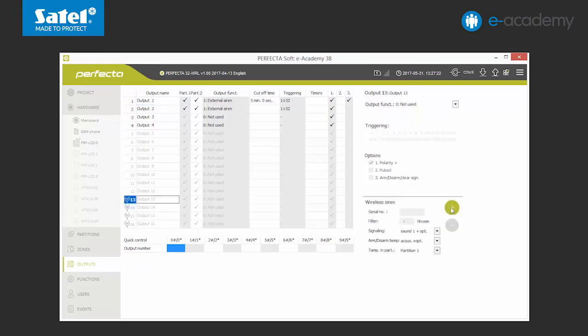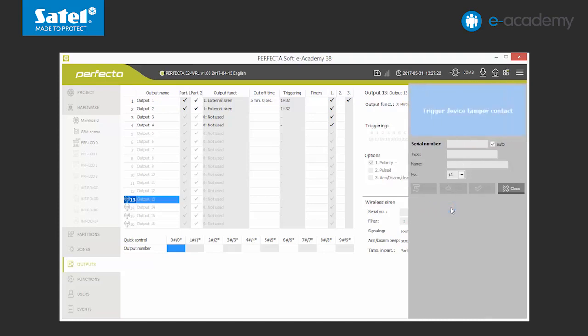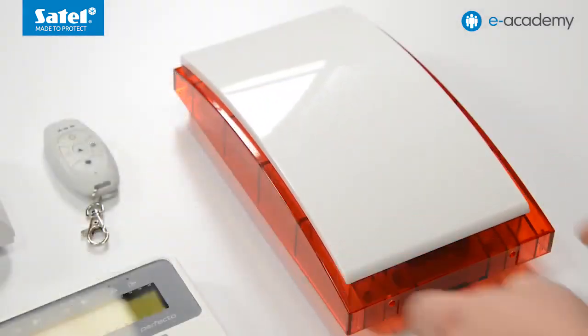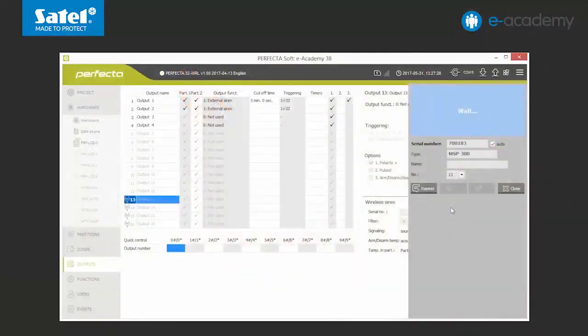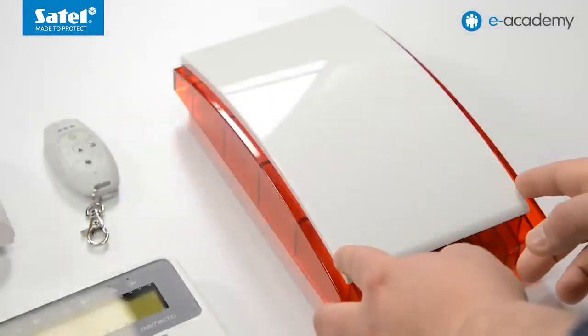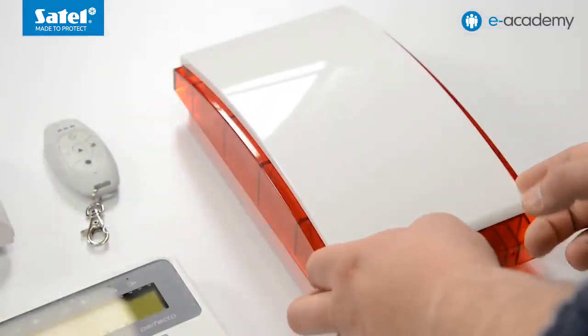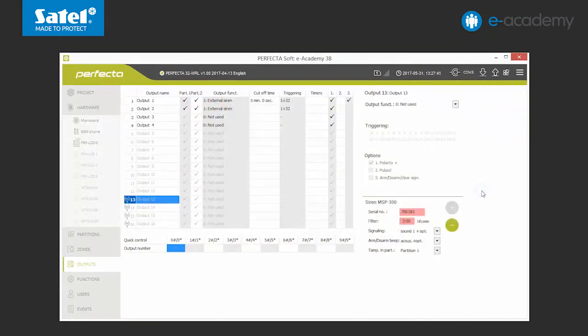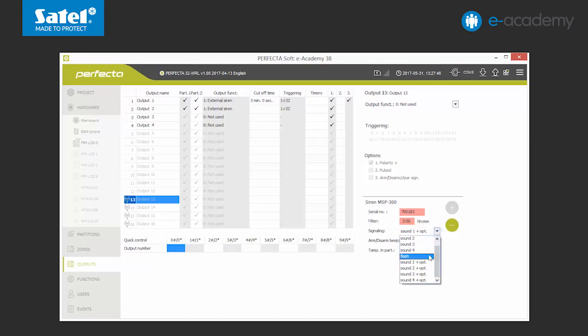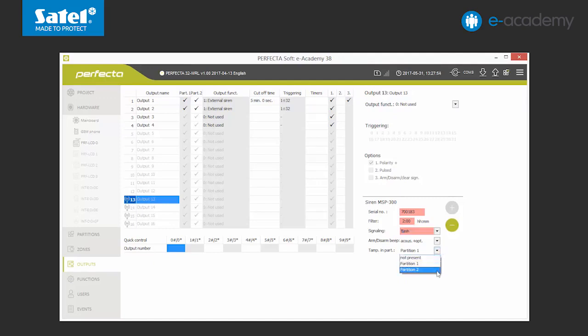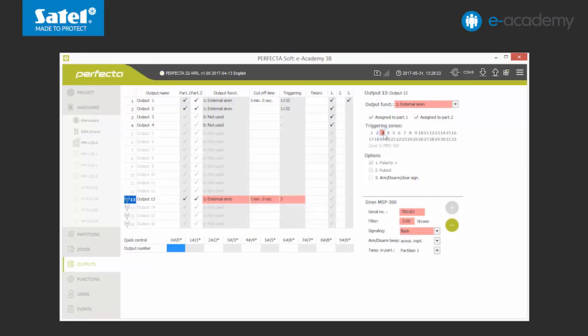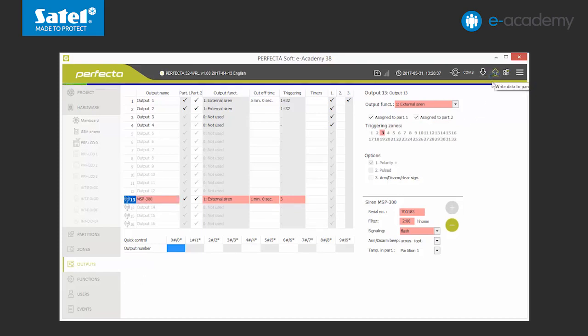Click plus. For our siren to be added automatically, we follow the instructions on the screen. We confirm by clicking OK. We can see that there are a few options available for the wireless siren. First, we choose the alarm type and the partition in which the tamper of the device will be signaled. We also choose the type of output, external siren, and set the time of its activity. One minute. We also have to define which zone will activate the siren. We can also change the name. Configuration complete. After the data has been sent to the control panel, the siren will be ready.